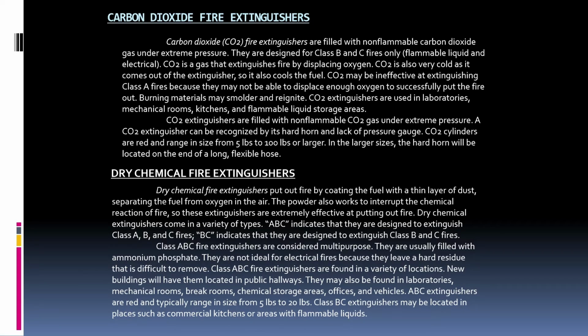CO2 extinguishers are filled with non-flammable CO2 gas under extreme pressure. A CO2 extinguisher can be recognized by its hard horn and lack of pressure gauge. CO2 cylinders are red and range in size from 5 pounds to 100 pounds or larger. In the larger sizes, the hard horn will be located on the end of a long flexible hose.